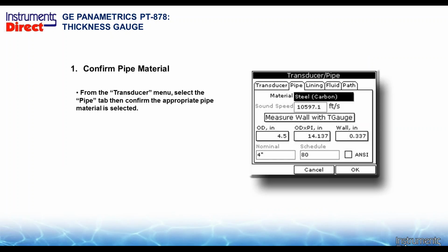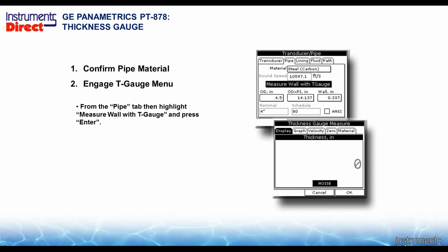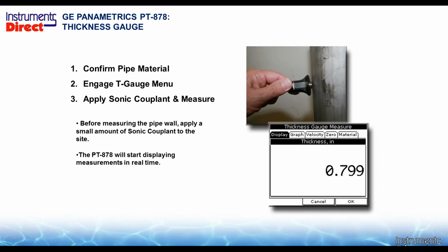You go ahead and plug it in the top of your flow meter, and from the transducer menu, select the Pipe tab, and then confirm the appropriate pipe material is selected. So once again, we need to know that they put in the right material there, so I can't just say steel all the time if I've got a copper pipe. Every sound speed is different, and it works accordingly. Put in the wrong data, and you get the wrong answer. So from the Pipe tab, highlight Measure Walls with the thickness gauge, and then press Enter.